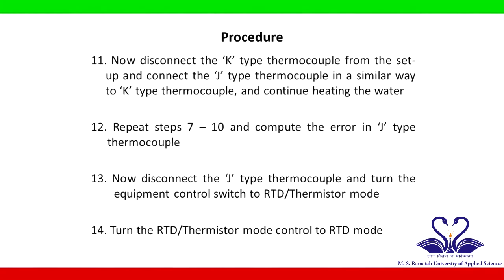Disconnect the K-type thermocouple from the equipment and connect the J-type thermocouple and continue heating the water. Repeat the steps 7 to 10 and calculate the error in the J-type thermocouple. Next, disconnect the J-type thermocouple and turn the equipment control switch to RTD or thermistor mode. Turn the RTD or thermistor mode control switch to RTD mode.